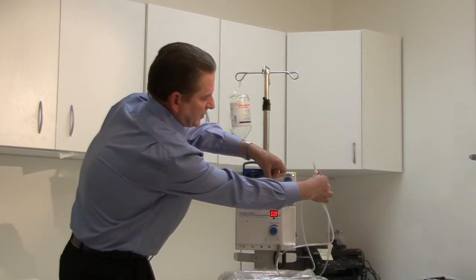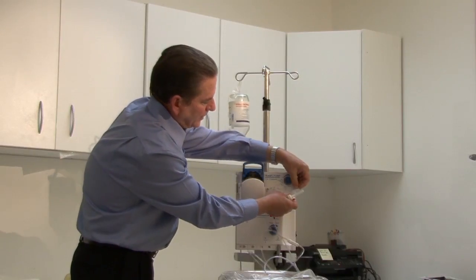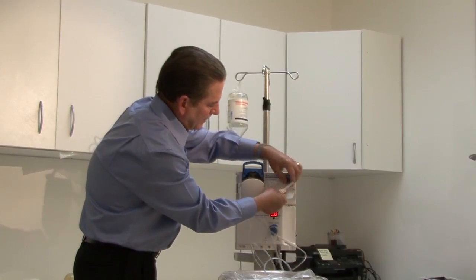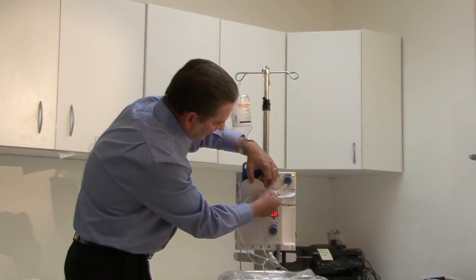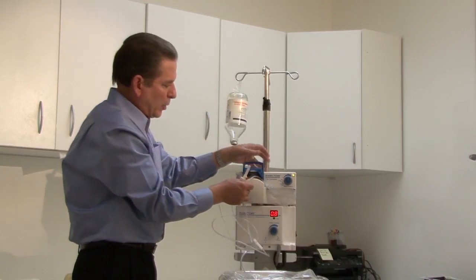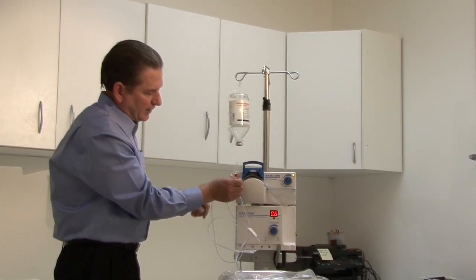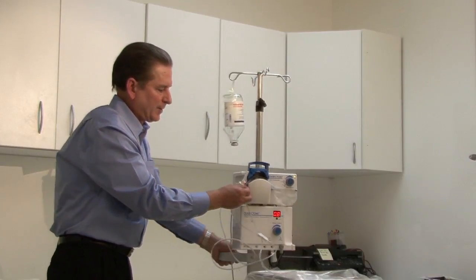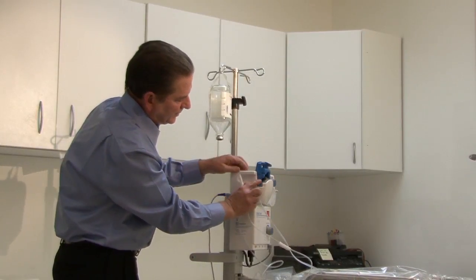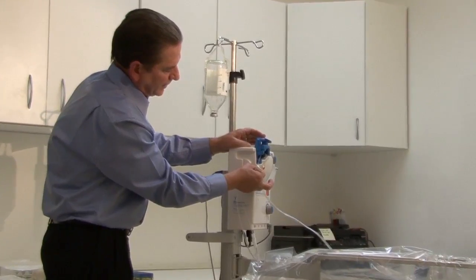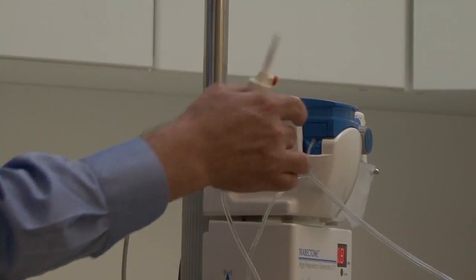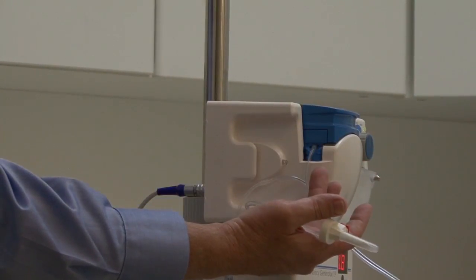We don't want to put it on so it's going the other way, so just go ahead and pop the little collection bag on here with the tube going toward the pump. With the pump open, you can see the little pump rollers. We're going to just lay that pump tubing right across the rollers, and I'll move it to this view so you can see. We can put just a little tension on that pump tubing and close the pump, and the aspiration is all set up and ready to go.